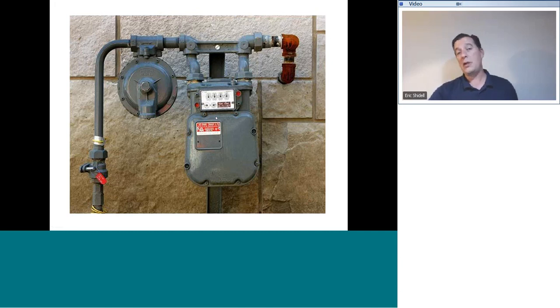This is really important when adding on things like tankless water heaters. The smallest tankless water heaters generally in use in a home for whole house use have an input rating in the 199,000 BTU range. That could be like the BTU capacity of a whole other house. And a lot of existing gas meters may not have the capacity to supply that much gas.